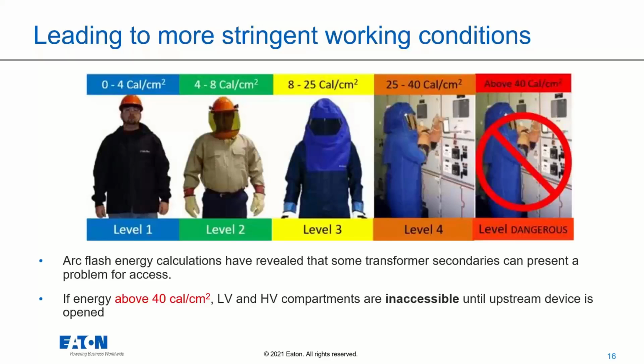So with that, you're typically targeting a level 2 zone where you're just wearing gloves and a face shield. That's typically what our customers are targeting due to the ease of maintenance, where you're just slipping on the gloves and the face shields, compared to level 3 or 4 where you're having to dress up in that big moon suit.